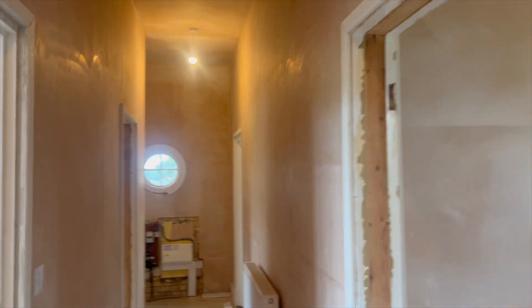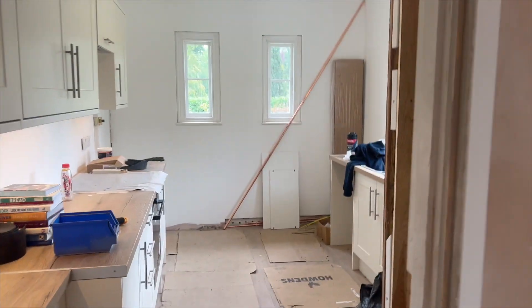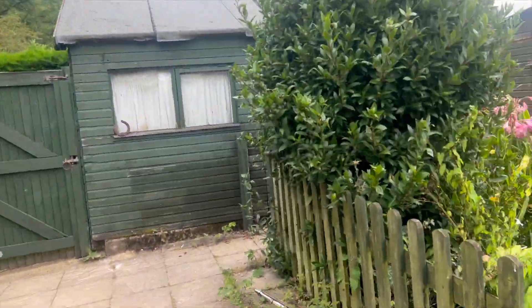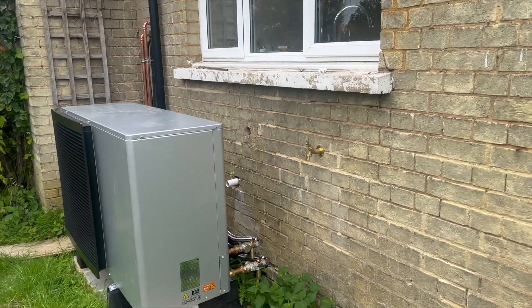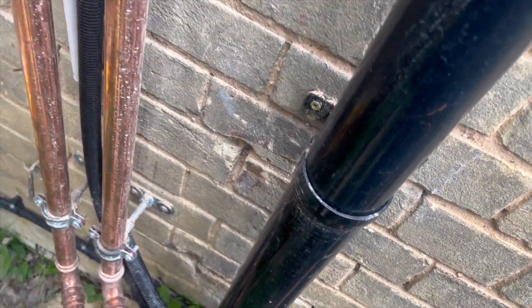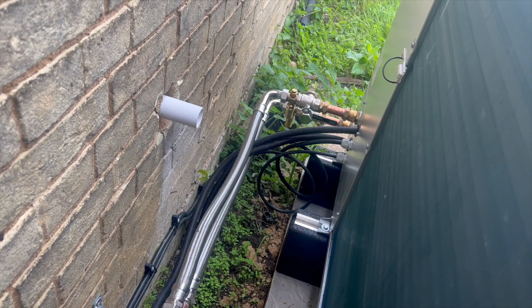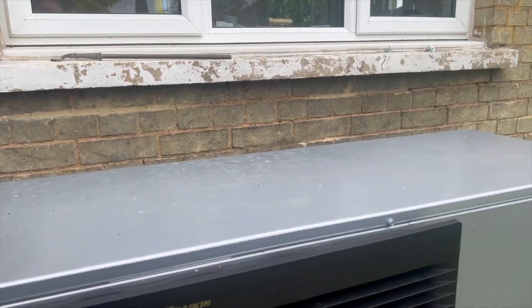We've also put a fan in as an extra - we're currently doing all the fans across all the properties because of the damp issues. The controller is nice. For the air source unit outside, we've got the Wiska box at the top and hi-tuf cable coming down. We've formed helixes on the cables going into the unit because obviously it vibrates when running. Our responsibility ends at the two isolators inside and outside - the air source installer takes it from there.